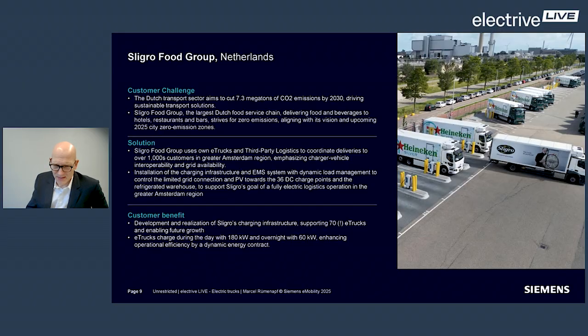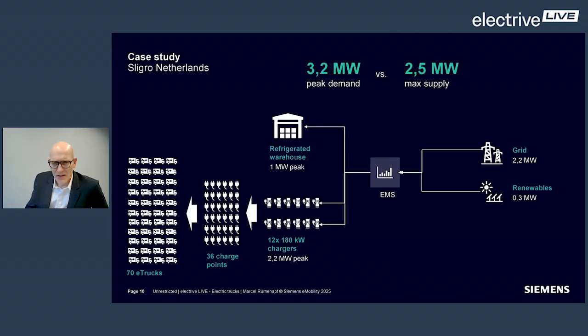I've visualized that on the next slide to give you a rough idea. On the left-hand side, that symbolizes the fleet of 70 electric trucks in their operation. These 70 trucks are charged by 36 charge points, which are powered by 12 chargers. Those 12 chargers have 180 kilowatt peak power each, adding up to 2.2 megawatt total potential peak power.